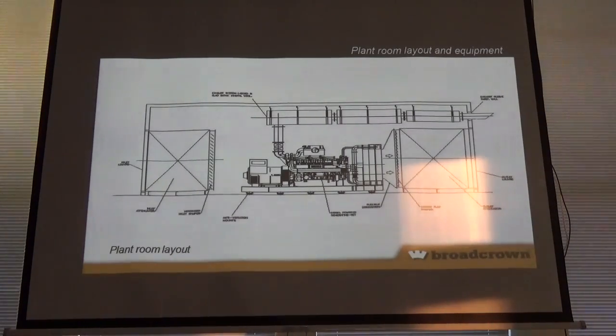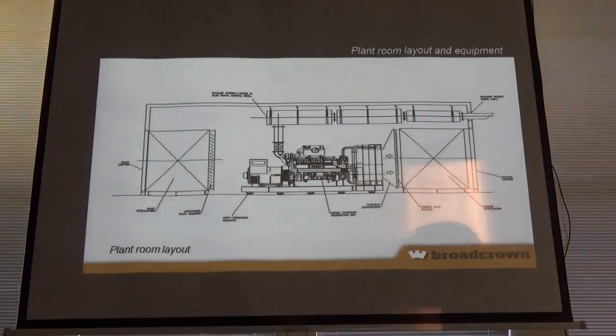For instance, it's equivalent to your car in the middle of winter time. You know, you go outside, very cold, you're not going to thrash it straight away, it's not going to like having loads put on it. So basically that set's always sitting there in anticipation of needing to run, and it's kept at the halfway house temperature, so to speak, so it has the best load acceptance even though it's not up to running temperature. So the key thing is they call it cold load acceptance temperature, and that's engine blocks up to 45 degrees centigrade. So if you get a set in a witness test or something and you're coming along first thing in the morning, that's the best thing to see what the performance is like, because in context of operation, you know, that's the closest to it.